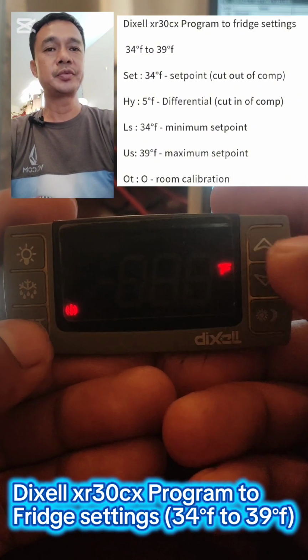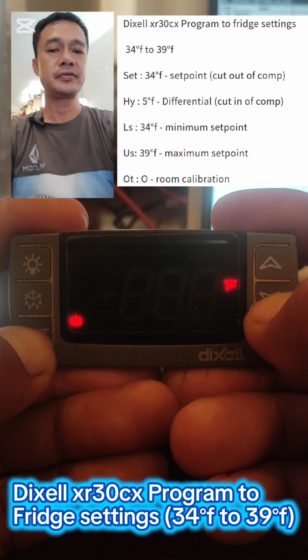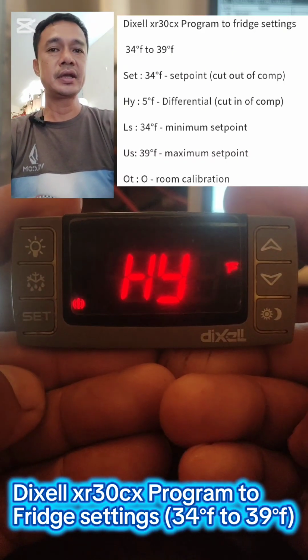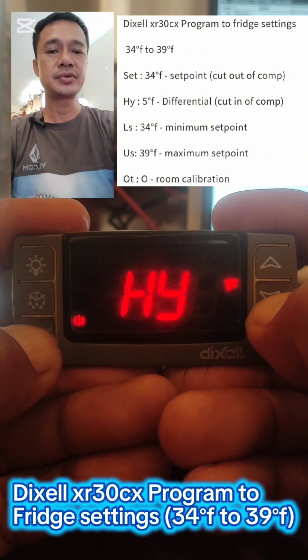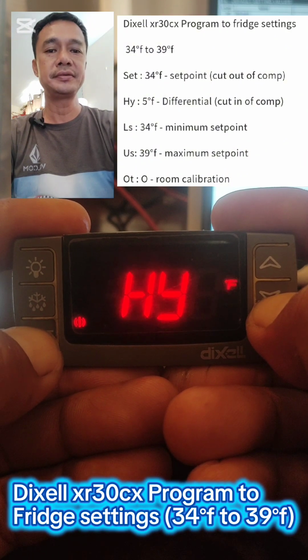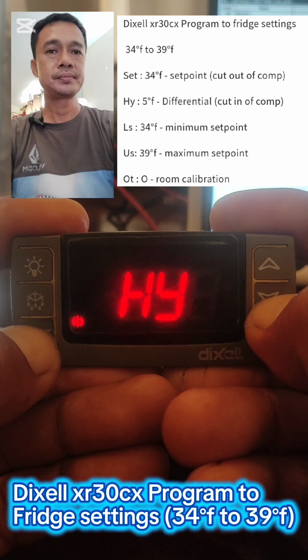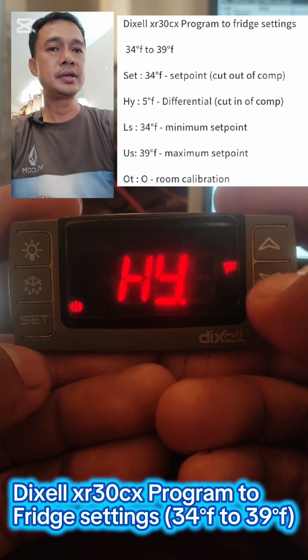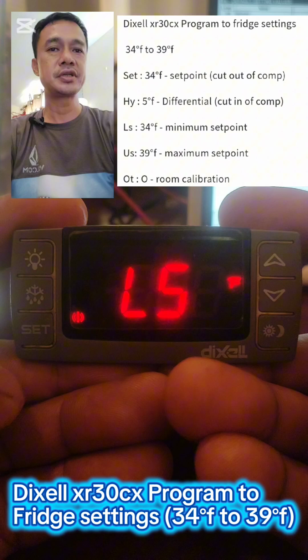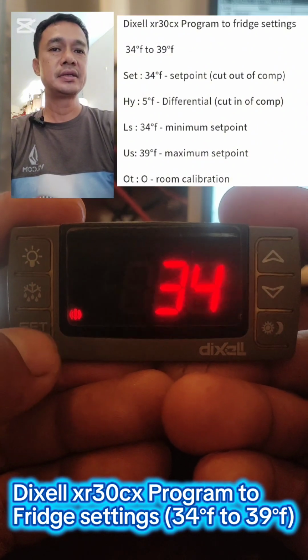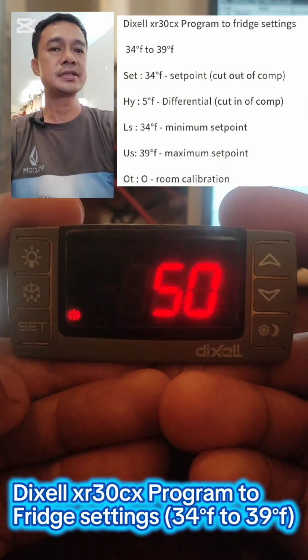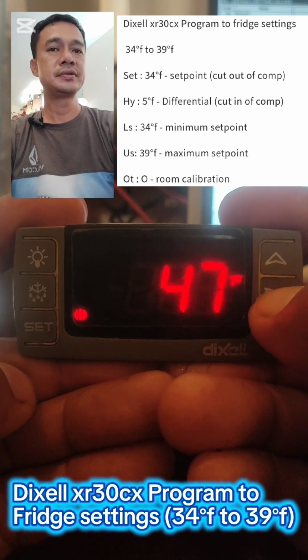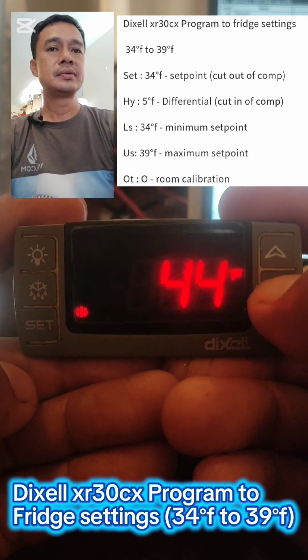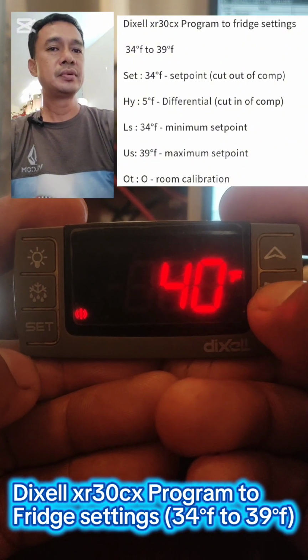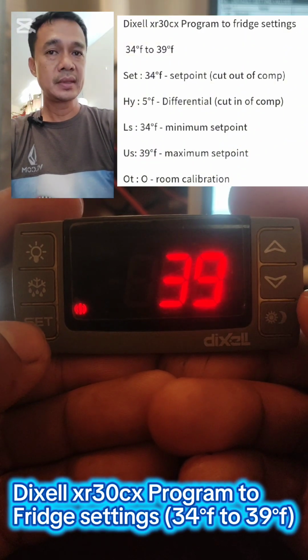And we're going to enter the programming again by pressing the set button and down button for 3 seconds. And another set button and down button for 7 seconds to enter the hidden parameter or hidden menu. Then let's go to US by pressing the up button. LS is already set to 34. US, we can now change that into 39, the same as my cut-in. Reset.